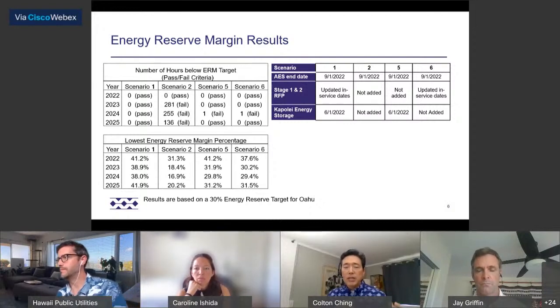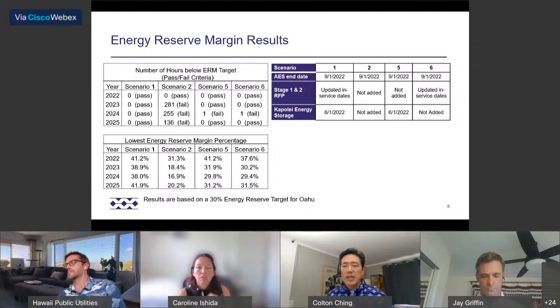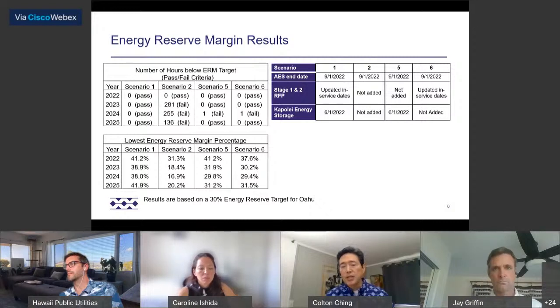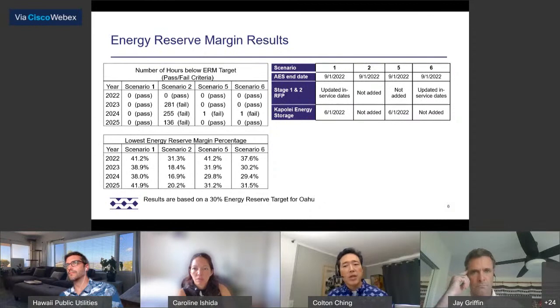But it really looks at using a production simulation. So the methodology relies on the use of our Plexos model to use a production system capability to look at the specific state of charge of that battery in that hour, the dispatch of firm generation, what's available, what's not available, the solar resource, again on a statistical basis of what amount of solar and what amount of wind can actually contribute to capacity to serve load in that hour. And then we make that percentage calculation.